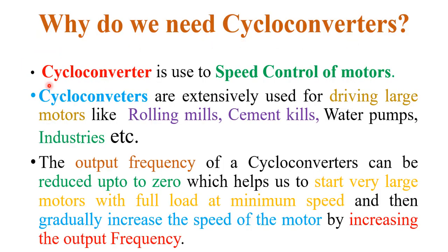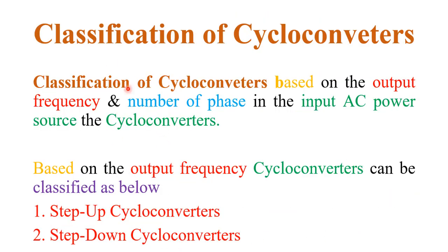Why do we need a cycloconverter? Cycloconverters are basically used for speed control of motors. They are extensively used for driving large motors like in rolling mills, cement plants, water pumps, and industries where large motor speed control is required. The output frequency of a cycloconverter can be reduced up to zero, which helps us start very large motors with full load at minimum speed, and then increase the speed by increasing the output frequency.